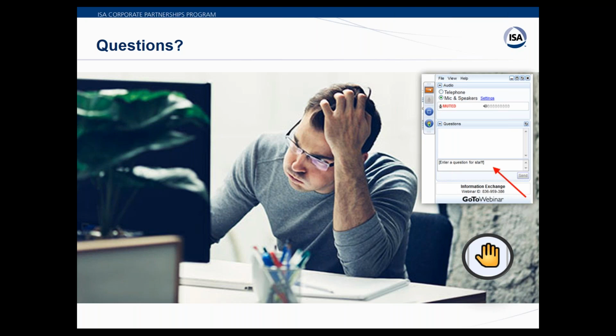All righty, does a 5-point calibration give better confidence than a 3-point check? Absolutely, because we're talking statistics. So more data means higher confidence. So absolutely, but it costs you money. You're basically doubling the time in the field, and if you're having to do an as found and an as left, it can be very significant. You know, it can add up.